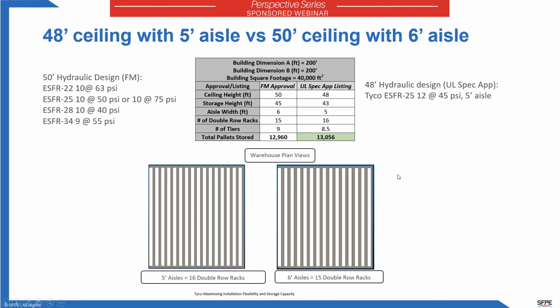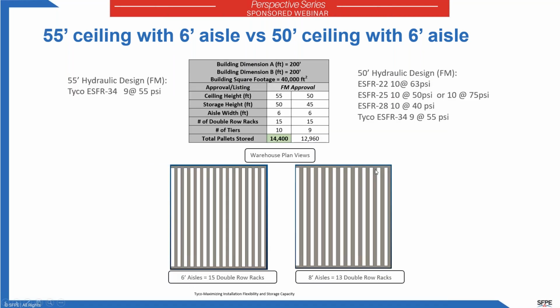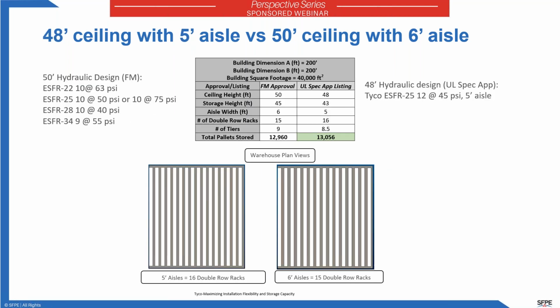Again, looking at the 45-foot ceiling, as I said, with the 6-foot aisles, and then let's look at the 55-foot. Oh, sorry, I went back. So the 48, similar to the 45 at 50, essentially the 48 versus 50 is the same. As I noted previously, the number of pallets that can potentially be stored under a 48-foot ceiling and 43-foot storage with a 5-foot aisle is essentially the same as the 45-foot storage arrangement. So again, these are opportunities where you can maximize your storage by understanding what the approved aisle widths are for the different sprinklers at different ceiling and storage heights.